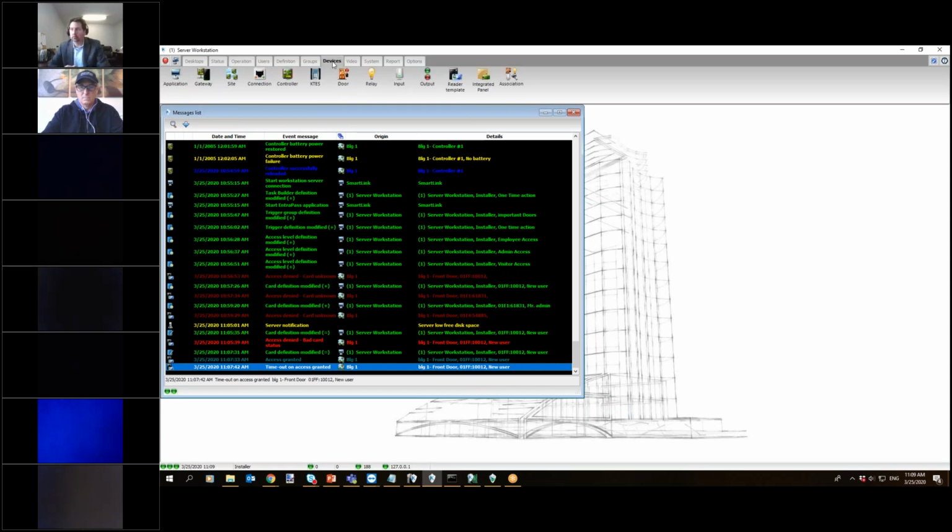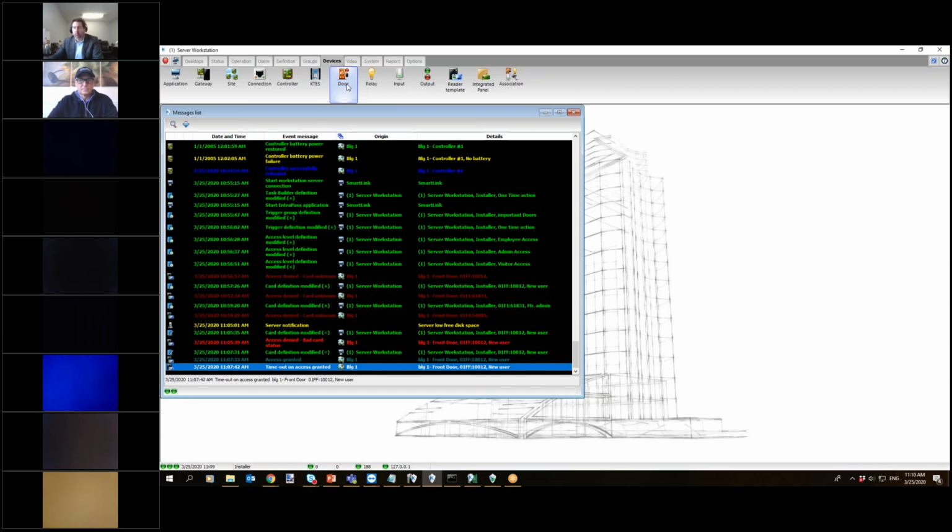The next lockdown, which is my preferred lockdown, is the door menu here. Now, this applies to all controllers except the KT200s and is available for corporate and global with a multi-site gateway and special edition also. So it applies to 90% of the market out here, right? And the only limitation is if you don't have a DSC panel. If you have a DSC panel, the moment you arm your alarm panel, it's going to apply the same settings and lock your doors down anyways. So as long as your alarm panel is armed, you won't have any problems here.